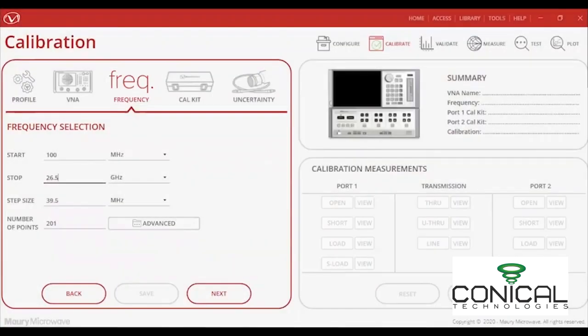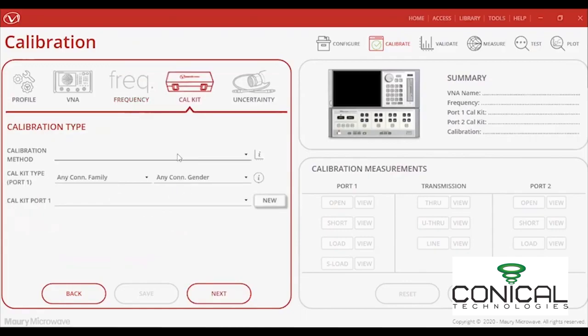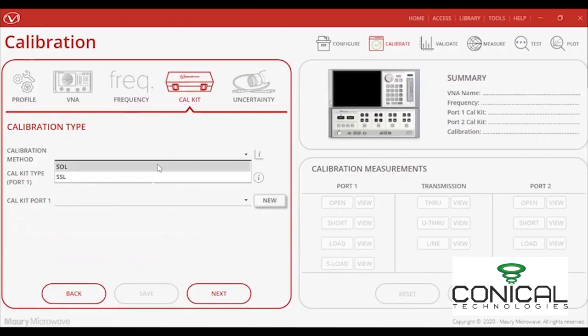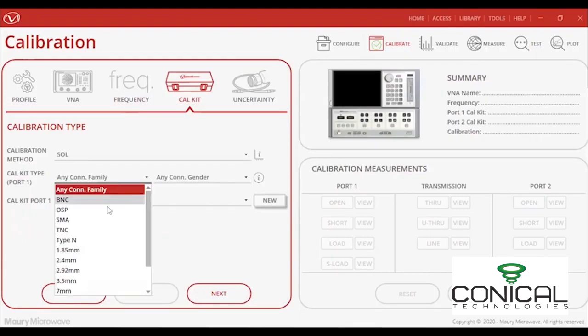I'll then set the frequency settings such as start and stop points, step size, and number of points all in one interface, unlike the front panel process of the 8510. Once the frequency range is fully set up, I can then select the CalKit and method of calibration. For the CalKit, either choosing between a polynomial CalKit or characterized CalKit with uncertainty.